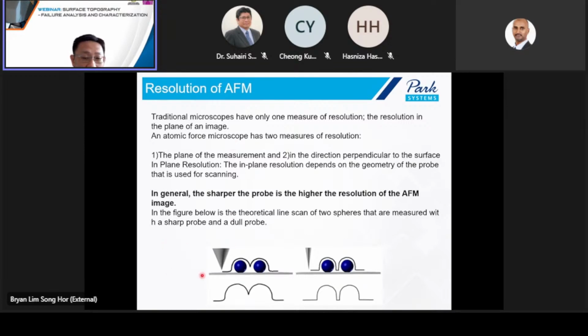So this is an example of the image using a dull probe. If we're using a probe which is not so sharp, as it scans along the feature, it cannot reach the bottom. So this is the 2D image that you get. However, if you use a very sharp probe, you'll be able to reach the bottom substrate and you can get this profile.